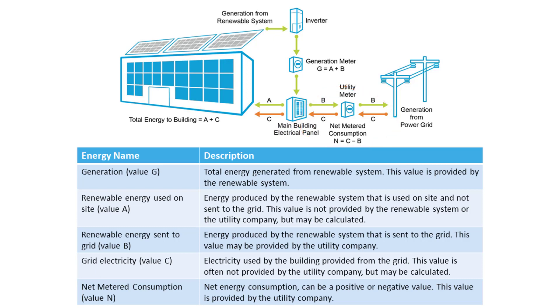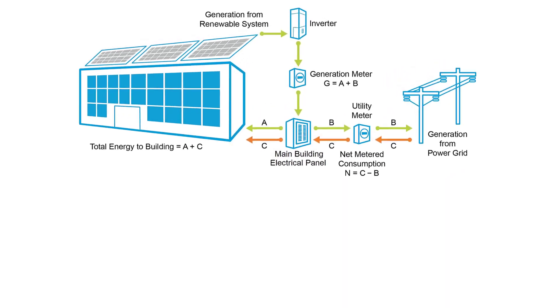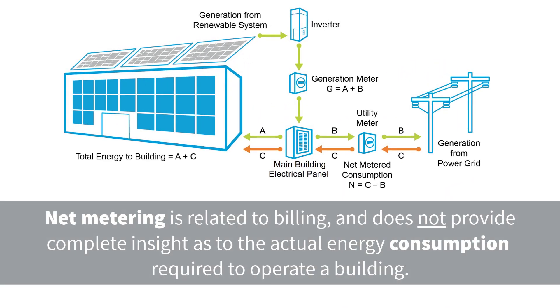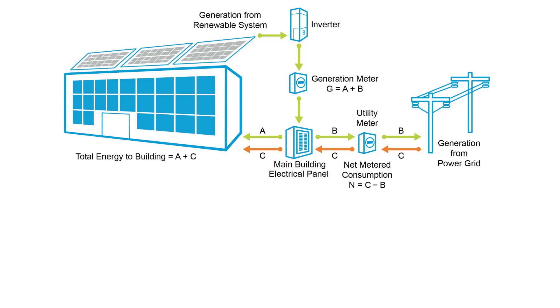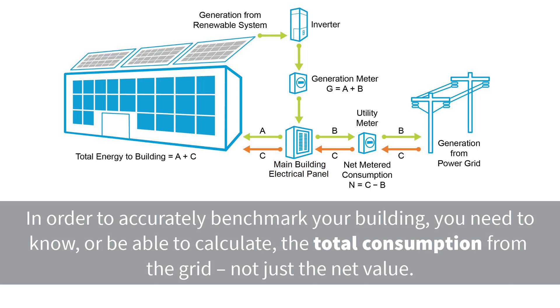A net metered value and its associated cost may be positive or negative in a given month. It is important to note, however, that the concept of net metering is primarily related to billing and does not provide complete insight as to the actual energy consumption required to operate a building. Even if a building is showing negative net metered consumption in a given month, and the customer is getting a billing credit because it sold back more energy than it consumed from the grid, the building would still have had to consume a positive amount of grid electricity during this period. In order to accurately benchmark your building, you need to know or be able to calculate the total consumption from the grid, not just the net value.